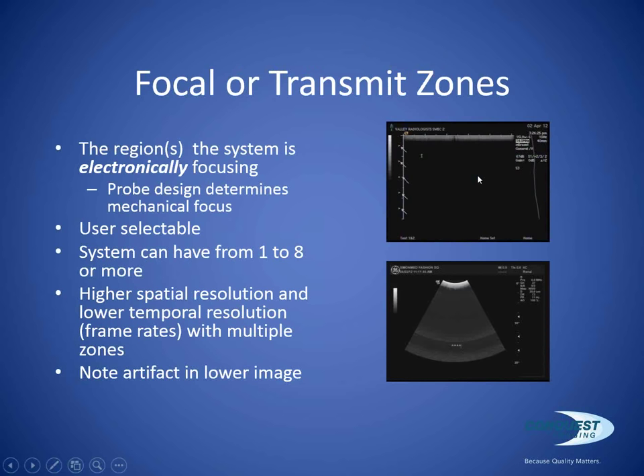There we go. This bottom image, you can see I have some arrows pointing to a left to right artifact within the image. It looks like an arc. And that is an artifact created by multiple transmit zones. When we use multiple transmit zones or focal zones, the system transmits to the first zone and receives that image, then transmits to the second zone, receives that image, and then pieces those images together electronically. You can get this artifact down below, and it's a focal zone artifact. This is not a malfunction, and this is nothing you can fix.